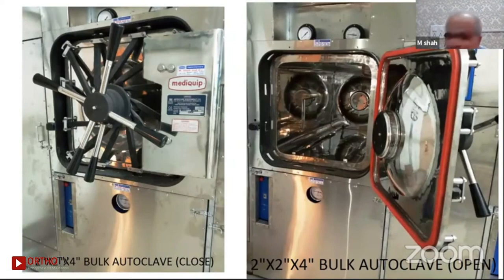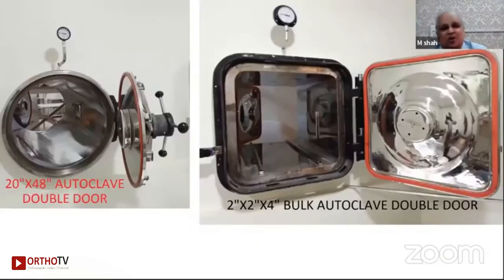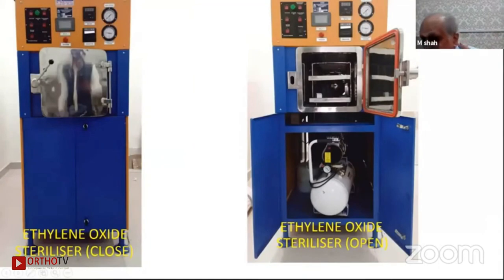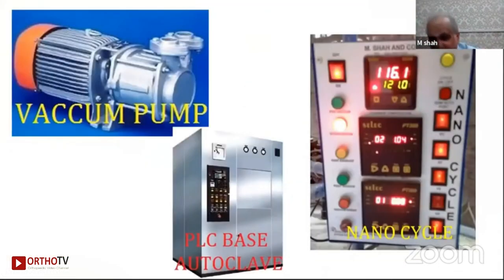Now, what happened when we inducted the vacuum pump? We could take the pulsing. What is pulsing? First, remove the air by vacuum, then induct steam, and then exhaust. With this, what do we do? We remove as much air in the chamber as possible. And Siddharth said that a chamber devoid of air is the ideal situation. So we tried to attain that and we came to a high speed, high vacuum autoclave. That reduced the time to 7 minutes, and the total cycle could be 30 minutes if you have a good autoclave.